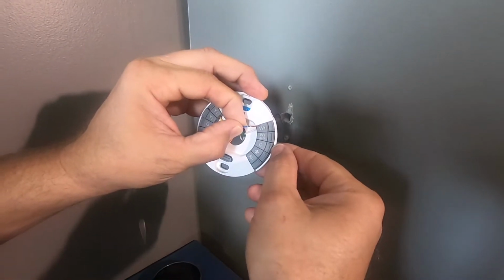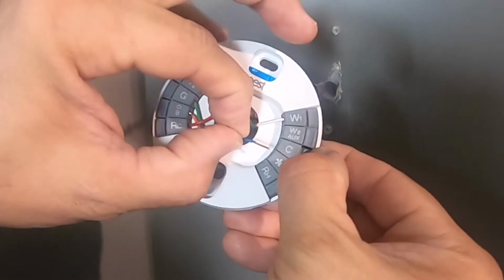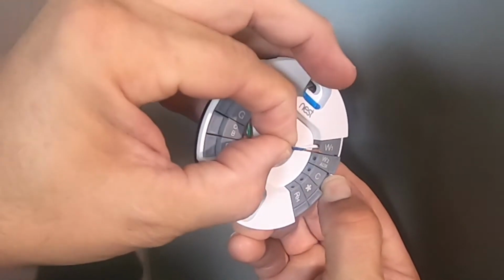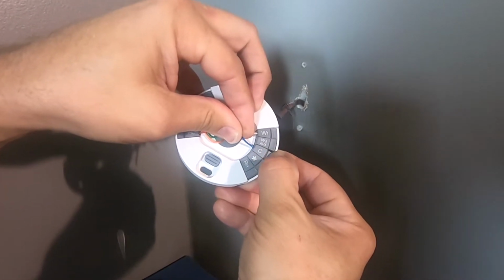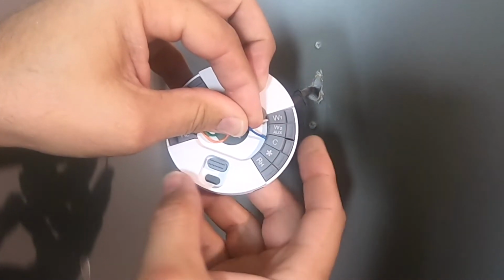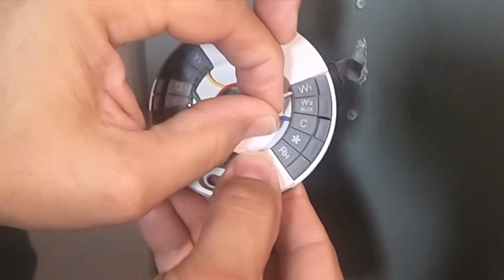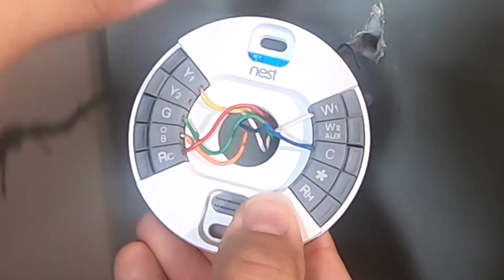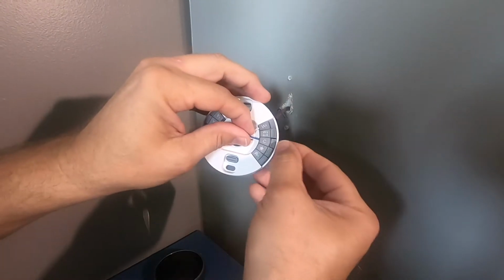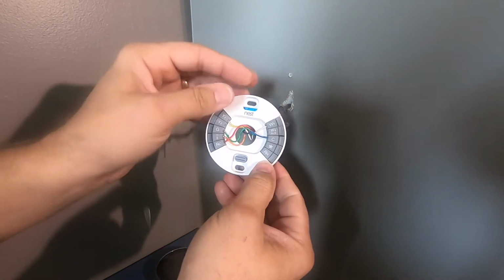So once you place this wire, you press the tab down and then feed the wire into the little hole there. And then once it's fed into the hole, let go of the tab on the right here. And if it stays depressed and you pull on that wire, it's in there tight. You're good. You've got good contact. If this tab pops up, you didn't get the wire all the way in.